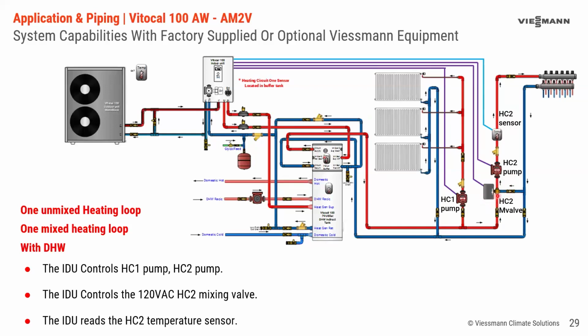In the heating mode, this mixing valve will modulate to maintain the hot water temperature based on your outdoor reset curve. And in a cooling mode, this valve just stays wide open. And this is going to be basically part of the logic that says, what temperature do we run this heat pump to for chilled water?